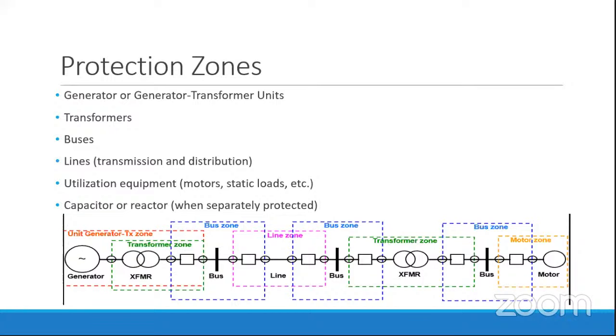Protection zone. Our substation has numerous electrical equipment: generators, transformers, bus, transmission lines, motors, and even utilization equipment like motors, static loads, capacitors, or reactors. So in order to protect the entire system, we need to divide this substation into protective zones, such that each will operate for its own fault only. And if that protection zone fails to detect a fault in the equipment, we need to have some backup protection. So the zones should be divided such that they provide primary protection as well as backup protection to the downstream network.